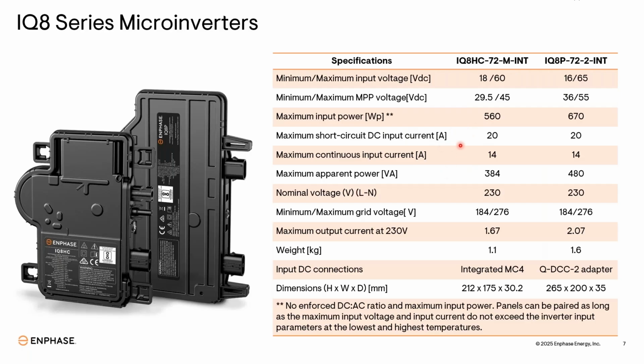Maximum short circuit current for both inverters is 20 amps, and the continuous current is 14 amps DC. Maximum output power from 8HC is 384 VA and 8P is 480 VA. The nominal voltage is 230 volt and the voltage range is 184 to 276 volt. The current output at 230 volt is 1.67 amperes for 8HC and 2.07 amperes for 8P. This output is AC from the inverters. Weight of the inverter is 1.1 kg for 8HC and 1.6 kg for 8P.